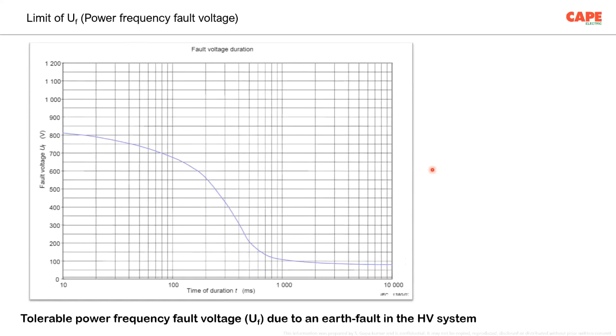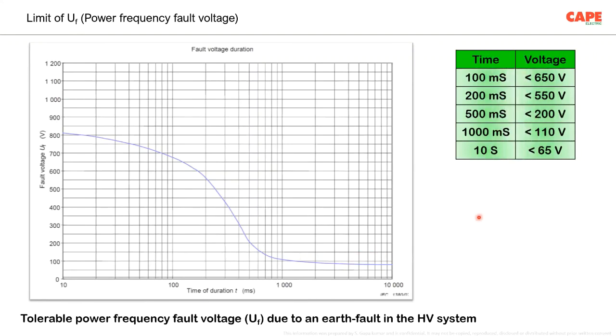Now, IS 732 has specified that under any circumstance, the shock voltage in an installation shall not exceed this particular graph. Your installation can be a low voltage, a medium voltage, a high voltage, extra high voltage, or whatever it is. The maximum allowed shock voltage is as per this particular graph. I just put it in the table. Within 100 milliseconds, the touch voltage shall be reduced to less than 650 volt. Within 500 milliseconds, less than 200 volt. Within about 1000 milliseconds, less than 110 volt. Within 10 seconds, about 65 volt. So this particular graph is used universally.